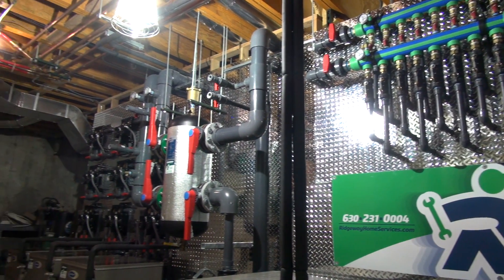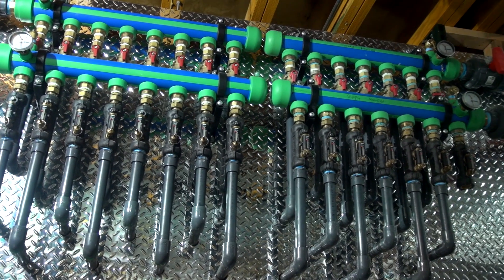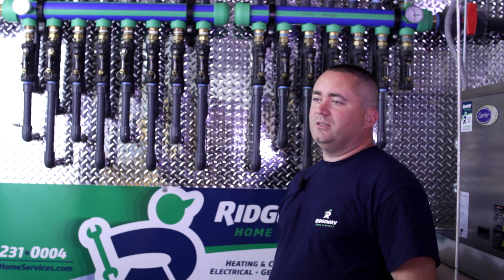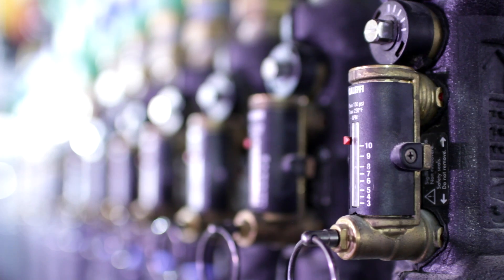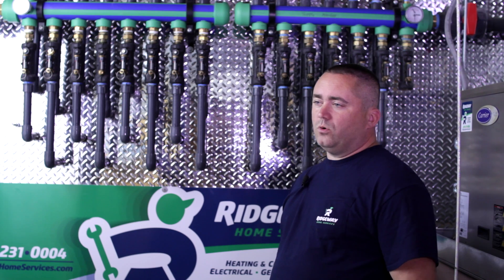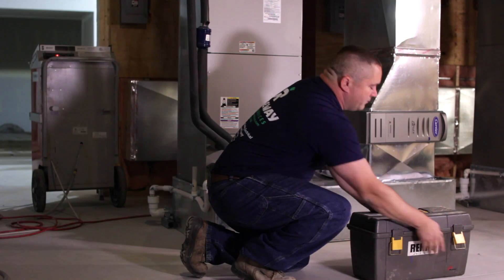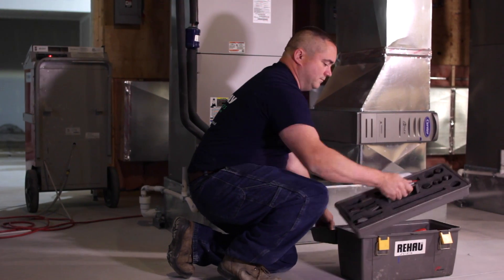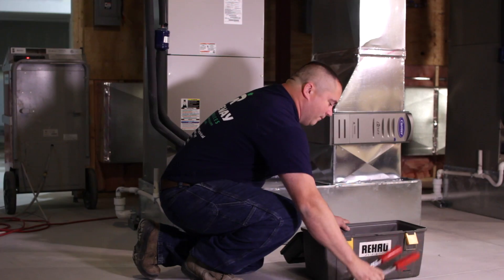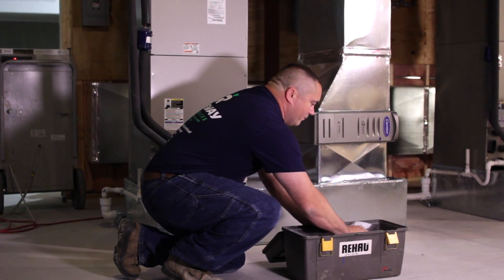Behind me is the Rau Geo manifold. We have 22 boreholes of inch-and-a-quarter Raupex coming into the house for 55 tons of geothermal. We have 18 loops with Caleffi circuit setters so we can balance each individual loop separately. Each of the 22 boreholes come into the house independent of each other, allowing us to purge and balance each of the loop holes, giving us the most energy efficiency out of the system.